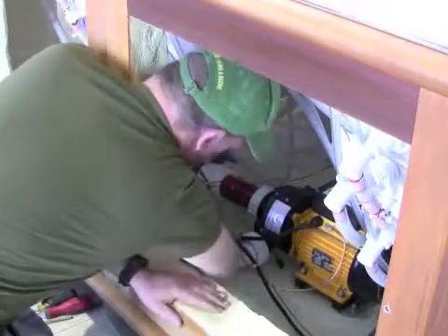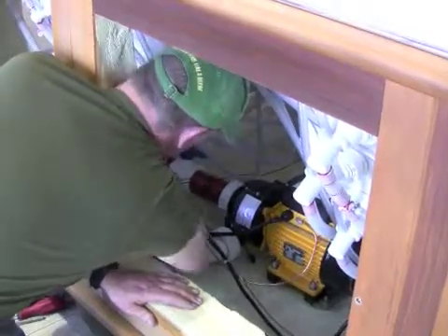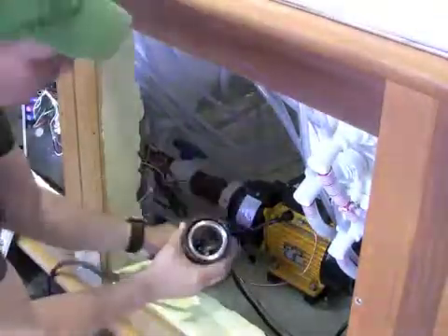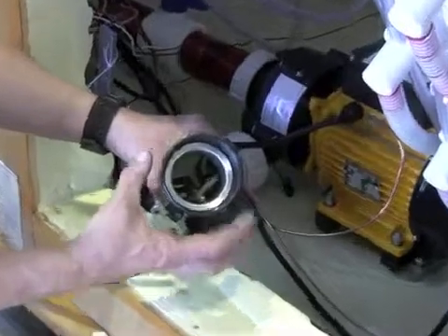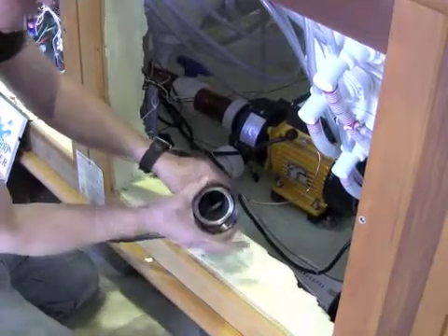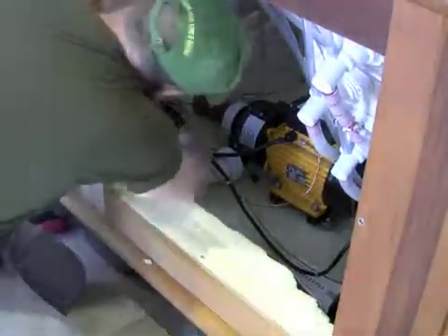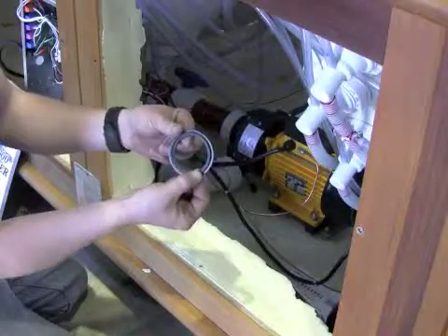Next, we're going to take a look at the heater union, which is the black one. This is called a split nut union because there are two screws on it, so it comes right in half and the nut splits in half. The reason for that is the steel flange around the heater, so you can actually replace the union if damaged. It's a two-inch split nut union, and inside is called a flat gasket O-ring.